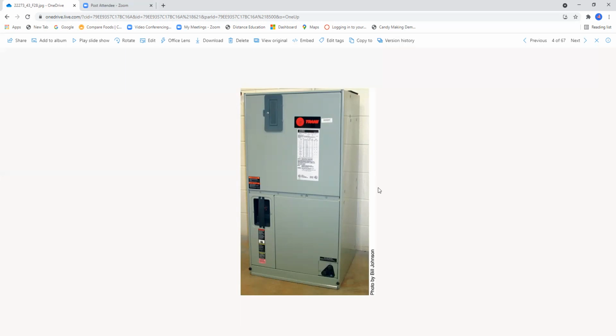Most of these cabinets are operated at 230 volts. They're typically not 115 volts. I haven't yet seen a 115 volt version of this. And also you have to run two circuits. Typically you're going to run one just for the heat pump operation, and then the auxiliary strip heat requires a separate circuit and bigger wire sizing in order to power up the heating packages that are installed.